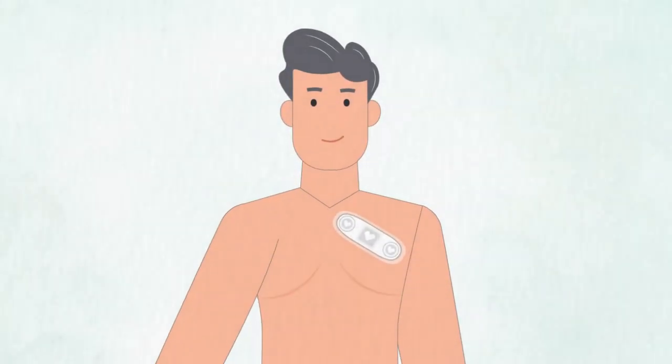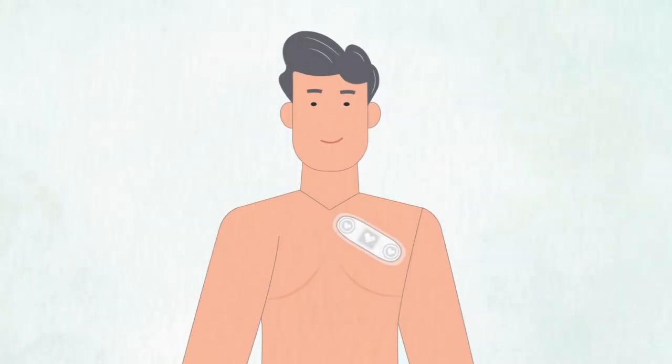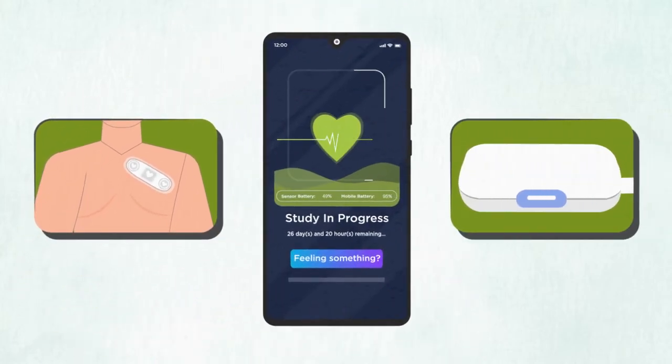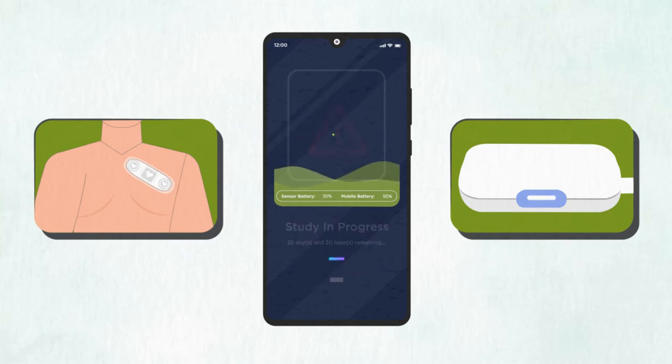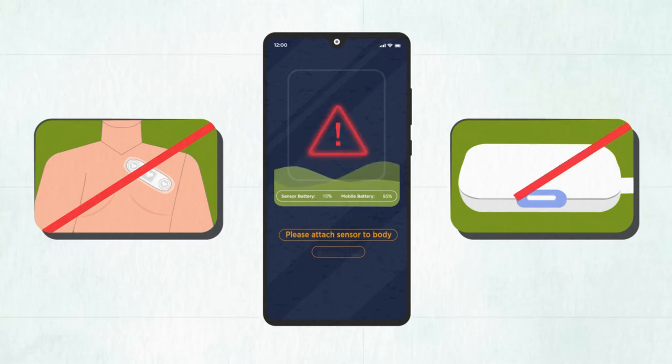Remove the sensor from the case and re-adhere it to your chest using a new adhesive from your kit. The sensor can only record data when it is properly adhered to your body and charged. The phone will alert whenever it detects that the patch does not have full contact with the skin or is low on battery.